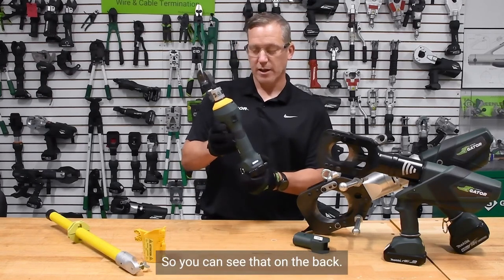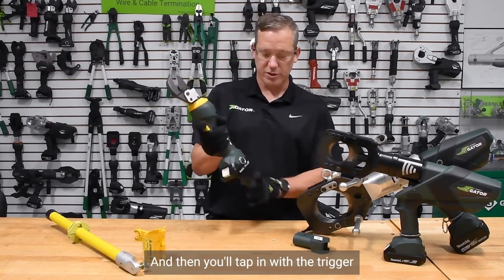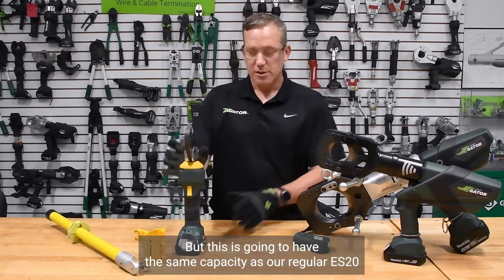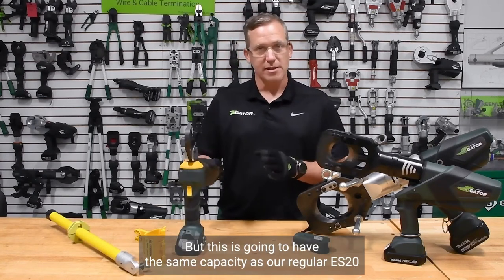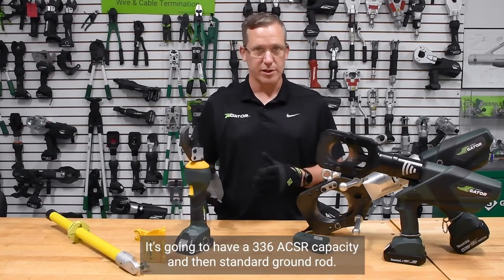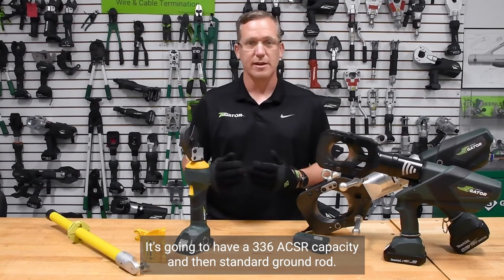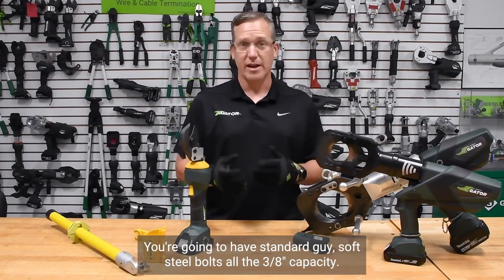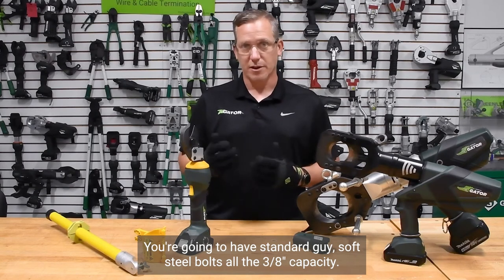You can see that on the back, and then you'll tap in with the trigger to make sure that the tool understands that's what we want it to do. This is going to have the same capacity as our regular ES-20 that is not remote control — a 336 ACSR capacity, standard ground rod, standard guy soft steel bolts, all in the 3/8" capacity.